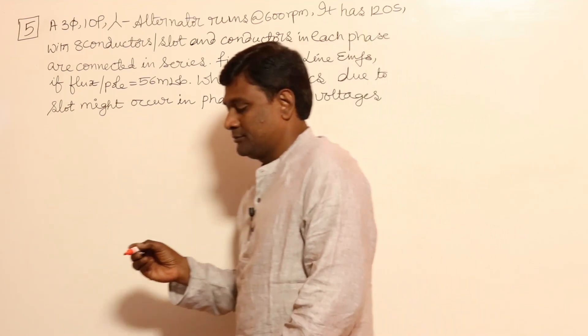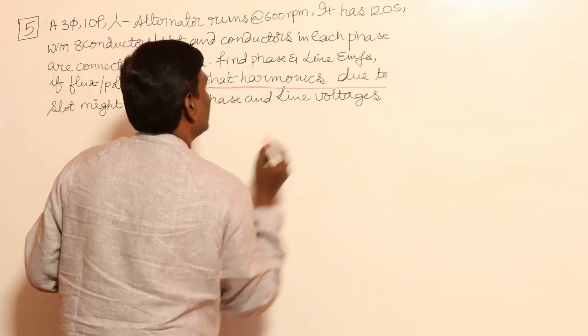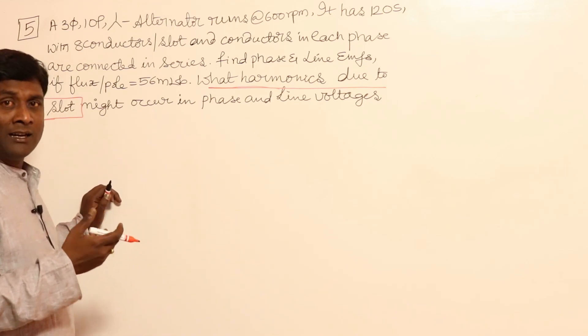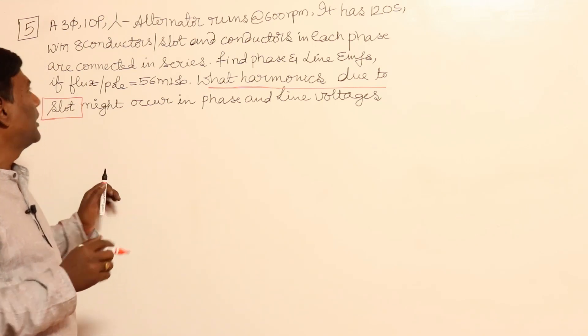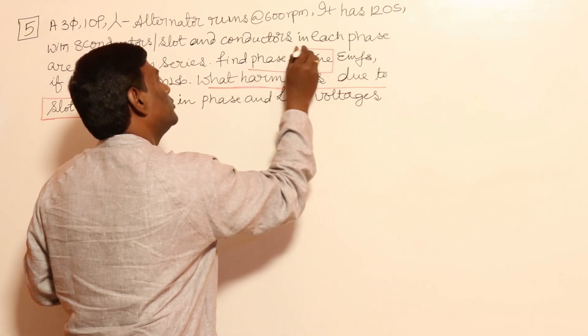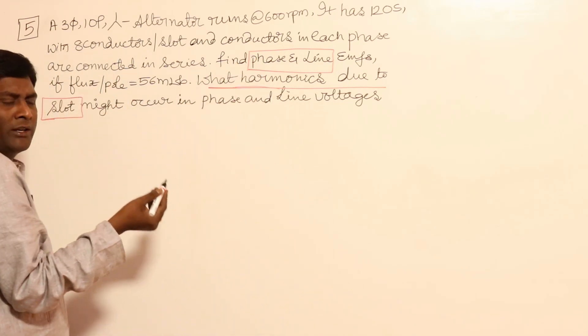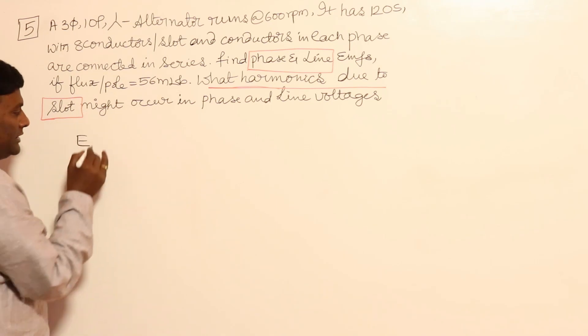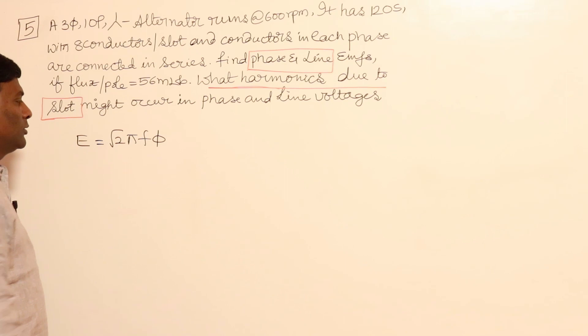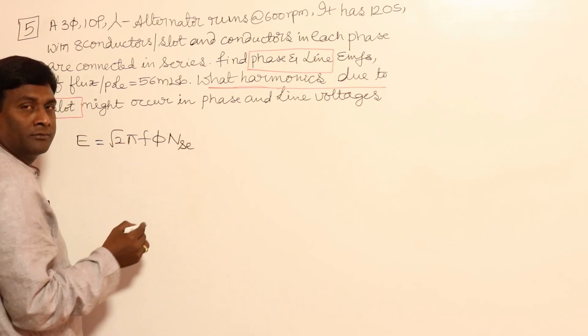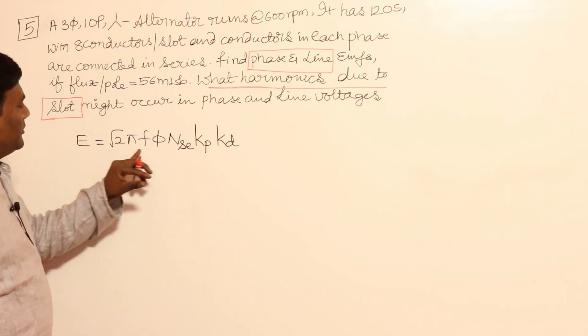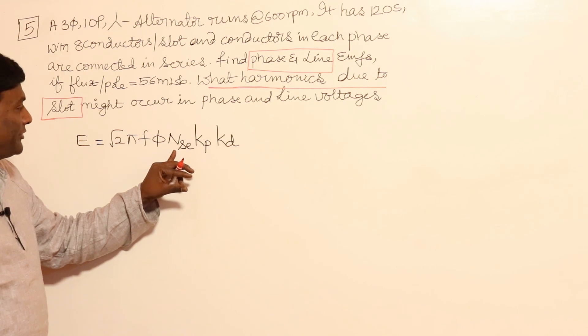What harmonics will occur due to slots — I may not be able to explain in detail, but I will tell you how to calculate. Now, induced voltage has to be calculated — finding the phase and line voltages. The induced voltage equation is the same as in a transformer: E = √2 · π · f · Φ_max, but here it's √2 · π · f · Φ · number of series connected turns, times Kp and Kd — the winding factor. This gives per-phase voltage.